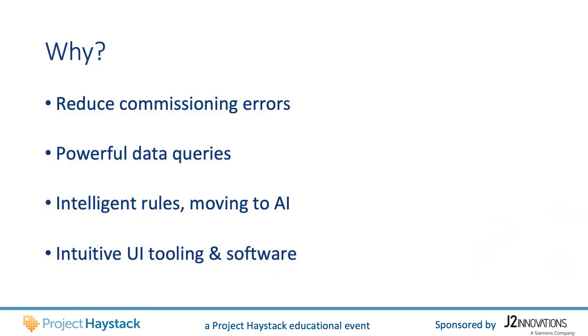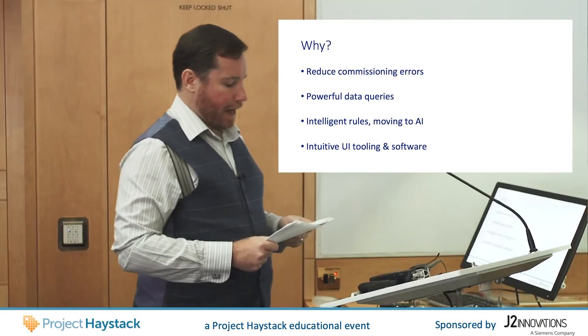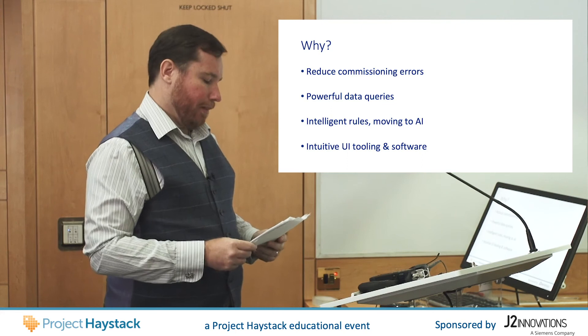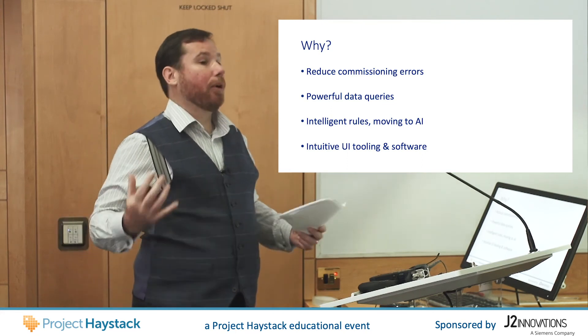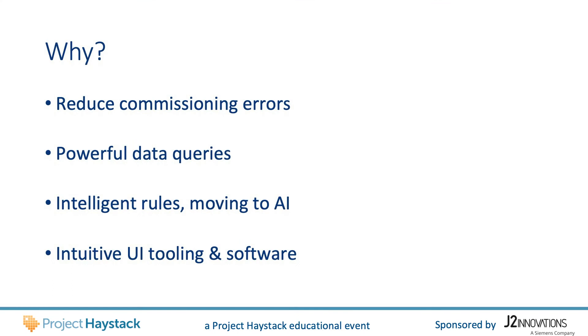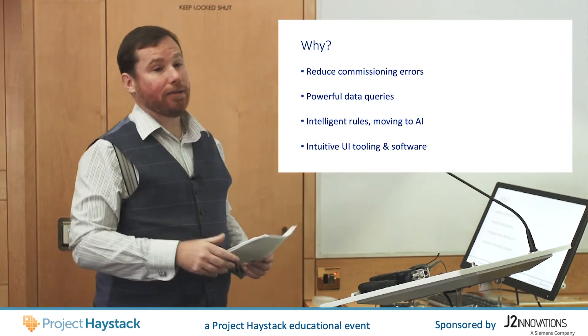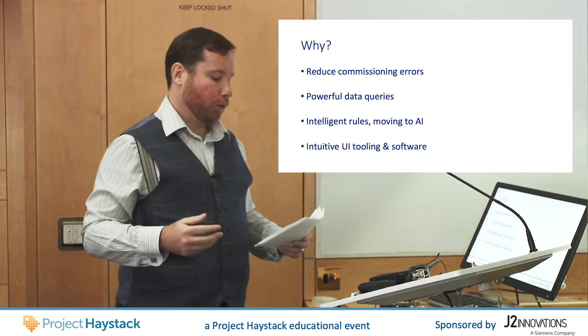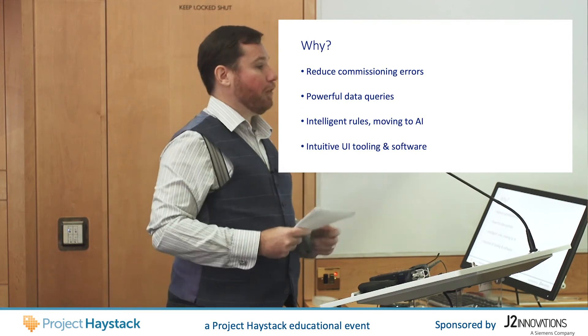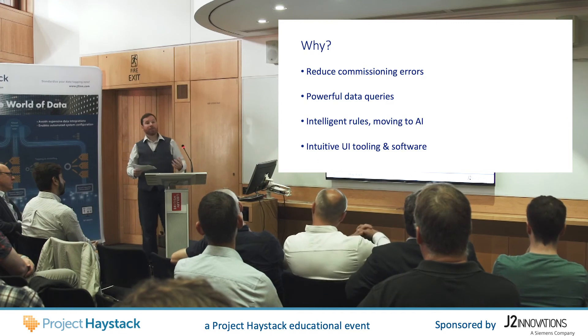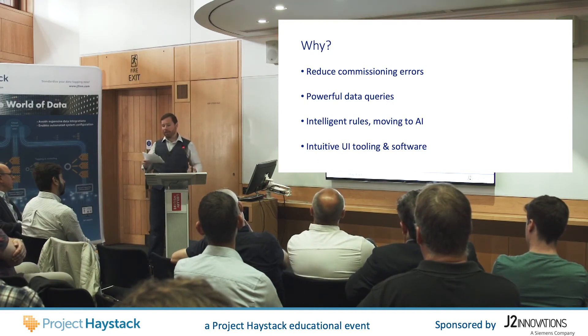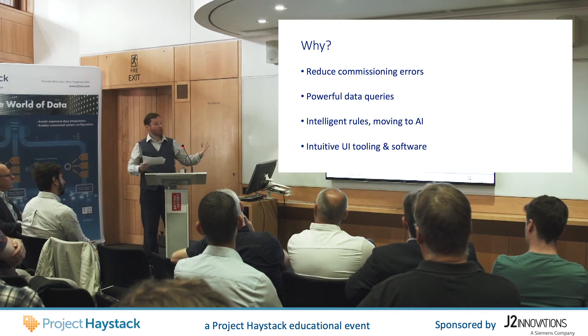I've talked about new formal tag definitions coming in Project Haystack 4, and how computers will understand more about the tags we already use today. But why bother with all of this? Well, going back to Dangerous Dave commissioning his building late one Friday evening, we can now more easily validate his work and check for silly mistakes. All this metadata around tags lets us perform powerful queries — I can search my building for all the equipment that heats air or conveys liquids. This gives rise to more intelligent rules for automation and analytics, which in turn could fuel future AI systems, and I can use these newly defined relationships to start developing more intuitive UI and software.